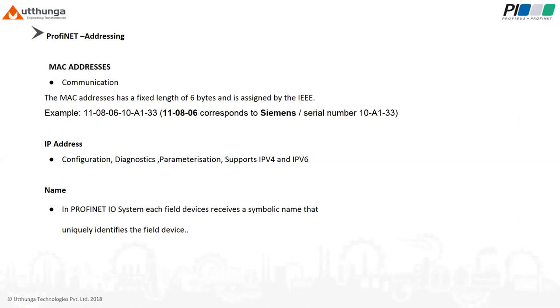IP address. The IP address is assigned based on the device name using a supervisor. The main purpose of IP is configuration, diagnostics, and parameterization. It also supports IPv4 and IPv6. Names. In a PROFINET IO system, each field device receives a symbolic name that uniquely identifies the field device. That is, the name is used to relate the IP and MAC address of the field devices.